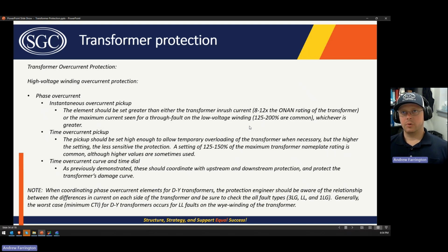So there are certain cases where, say that it's a 10 MVA transformer, but there's only 7 MVA of available fault current at the transformer location because it's put into a weak system. Well, you don't necessarily need to set the instantaneous element to account for 10 times the ONAN rating of the transformer because it's not capable of even sourcing that much fault current. So that might be an instance where you look at the low side fault current and take a conservative multiplier on that, 125, 150% of the fault current seen by the high side of the transformer for a low side fault, set it above that, and now you're going to be safe for inrush, and also be secure for low side faults. Make sure you're not going to misoperate.